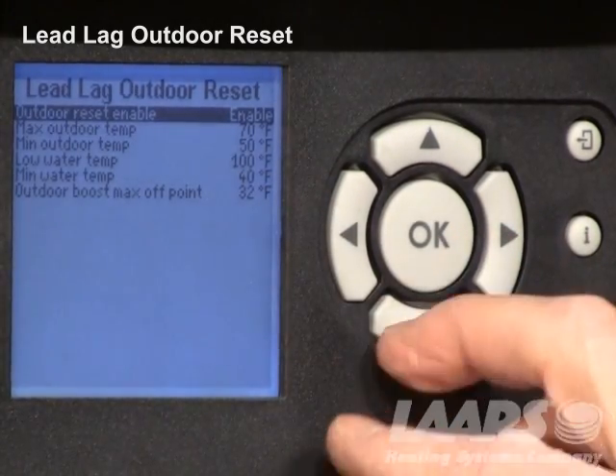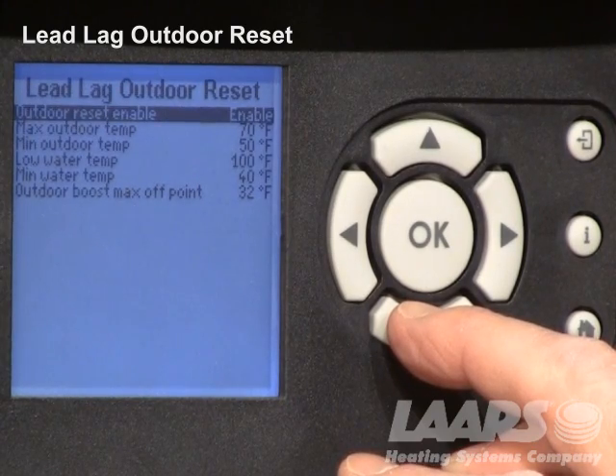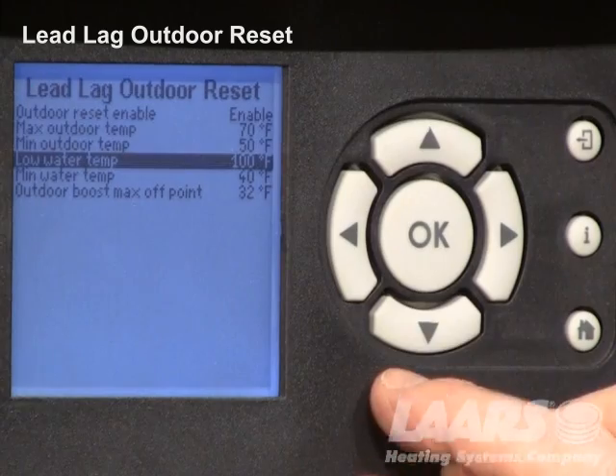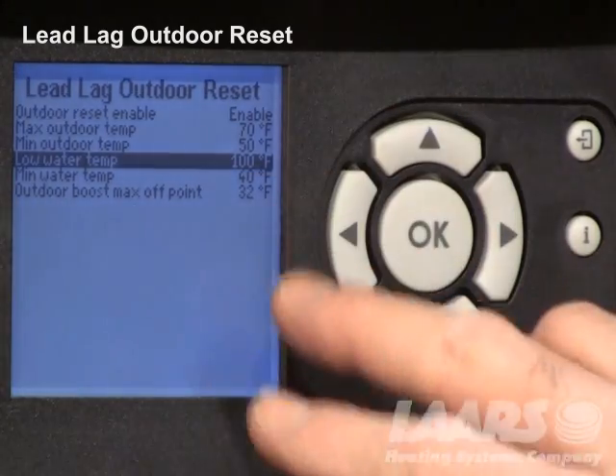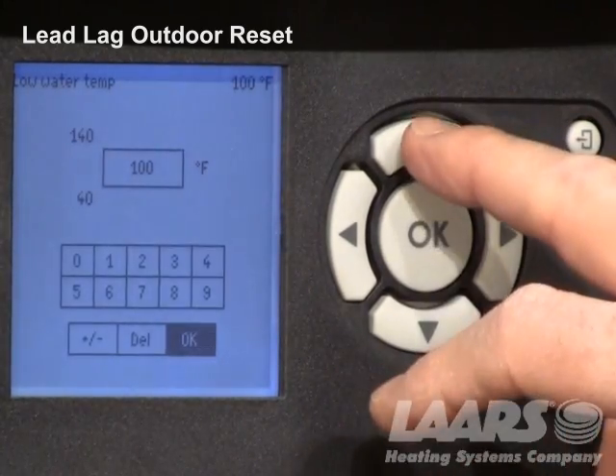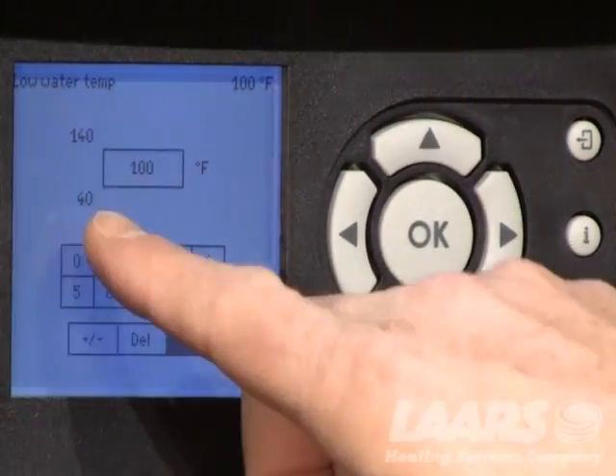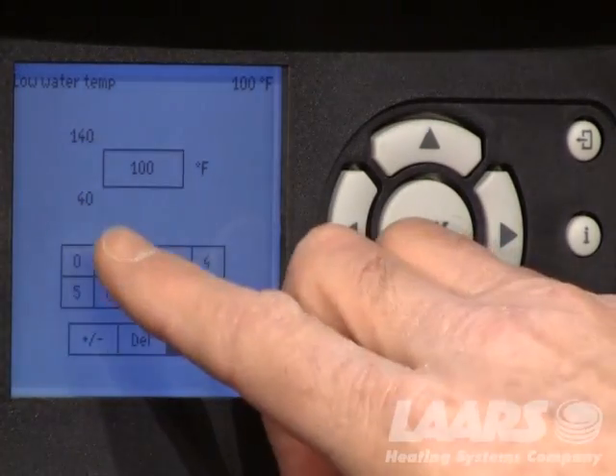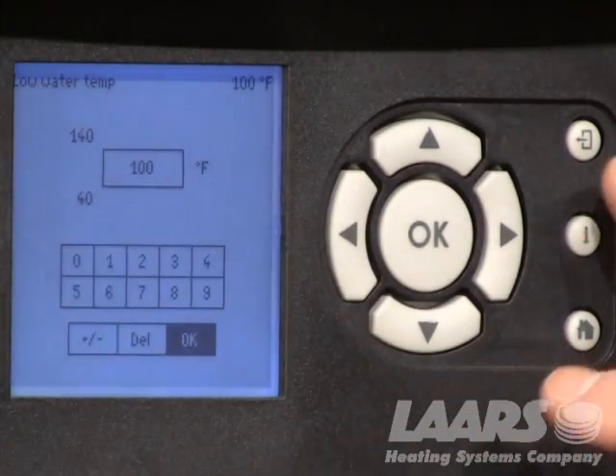This is the screen where you set your high outdoor or max outdoor temp, your minimum outdoor temp, low water temp, et cetera. If you want to change something, just highlight it and use your up and down arrows to make that change. The range on the left-hand side of that screen goes from 40 to 140 for the temp setting.